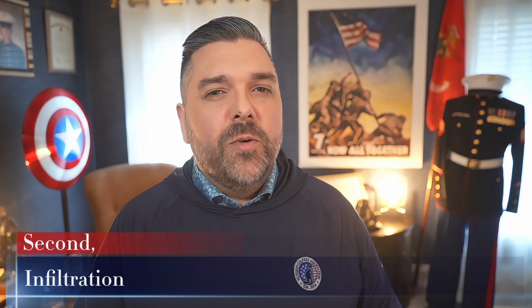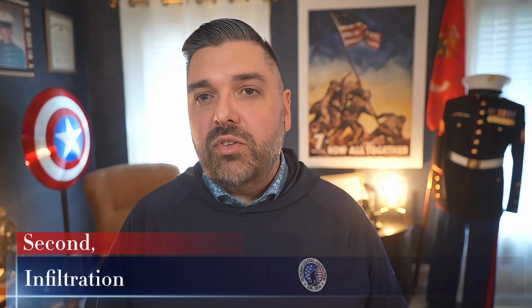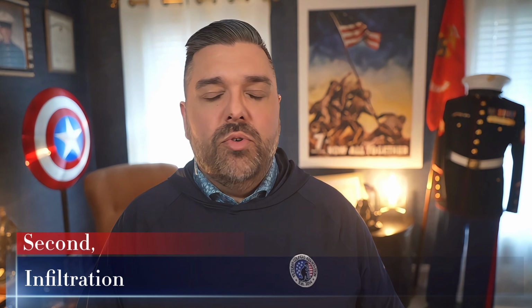Now let's talk about the one that inflates heating loads and sends contractors chasing equipment size they don't need: infiltration. Infiltration is the uncontrolled air leakage into and out of a building through gaps around windows, electrical outlets, through every little crack and penetration in the building envelope. It's a real load. It's a significant load in older homes, and it is almost universally entered wrong.